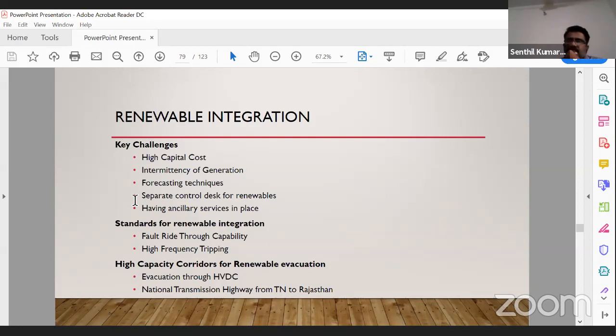High capacity corridors for renewable evacuation use HVDC lines. Right now we are establishing the Raigarh–Pugalur line, an 800 kV HVDC, 6,000 megawatt line from the eastern region to Tamil Nadu southern region, commissioned last month. On a single pole they can transmit 3,000 megawatts from Chhattisgarh to Pugalur in Tamil Nadu's southern region, and power transfer is possible both ways, from Tamil Nadu to Pugalur and back.